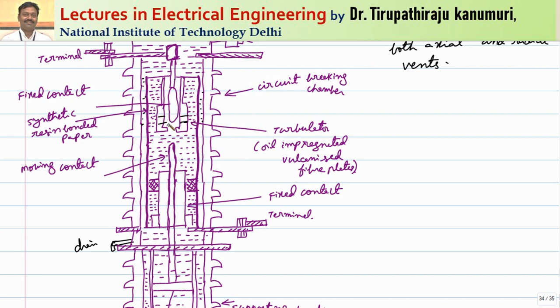To summarize: when the fault current is less, gas escapes only from the top axial vents and oil enters inside to extinguish the arc. When the fault current is of large magnitude, the radial vents also open, elongating the arc. As gas escapes through these radial vents, oil comes in from outside and the arc is extinguished more easily. The vents on the upper side open first, followed by lower ones one by one, so oil enters progressively as the arc length increases.